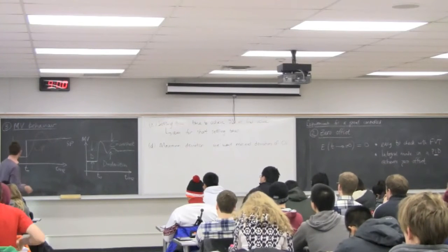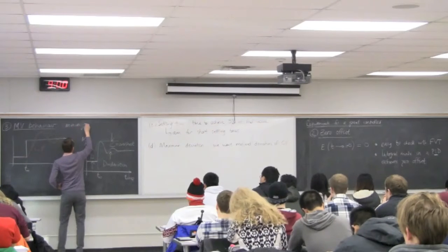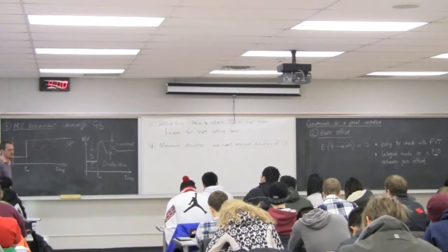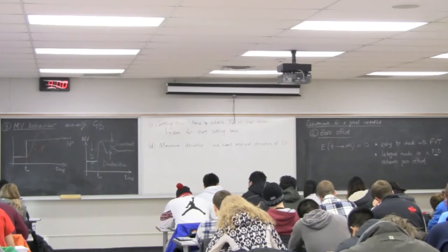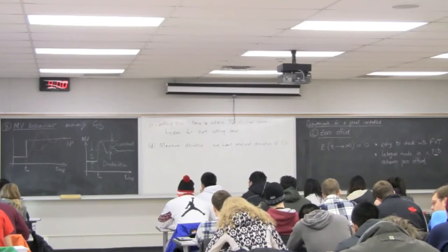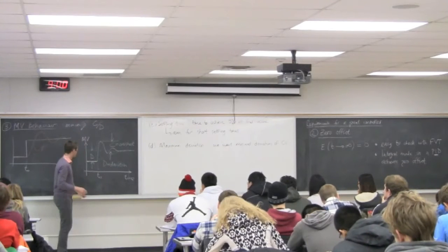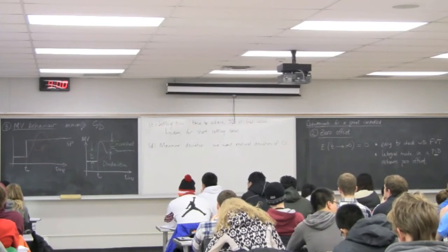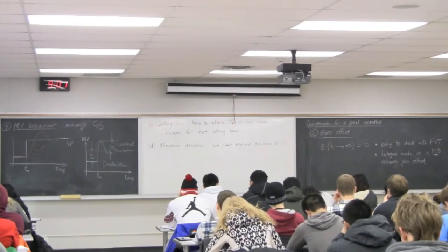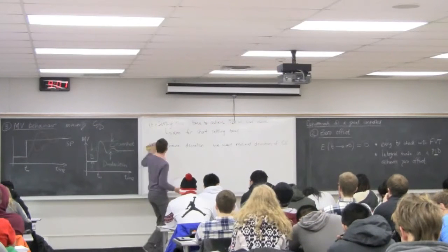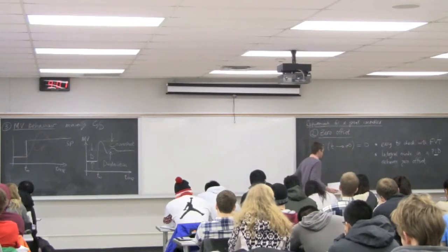Okay, so one requirement when we analyze the manipulated variable behavior is we want to minimize C divided by D. So we want to minimize our overshoot divided by the total deviation. And it should be clear that the smallest value you can get for that is 1. C over D, the smallest value you can assume is 1. If it's greater than 1, you've overshot and you've put more energy into your process. Okay, so those are three ways we can quantify our behavior. Now let's take a look at how we can achieve controller tuning that has aspects of this good behavior.